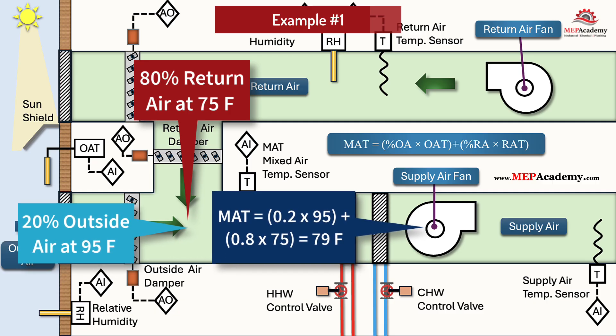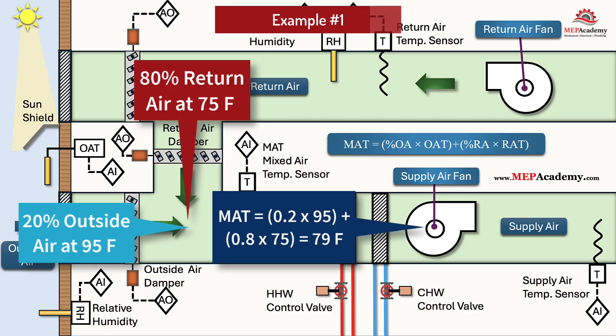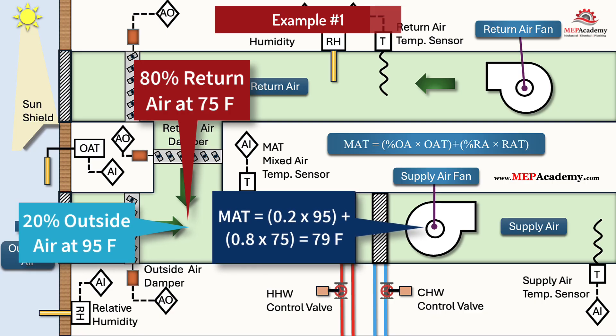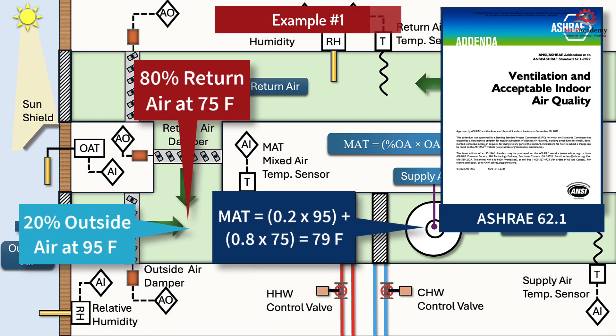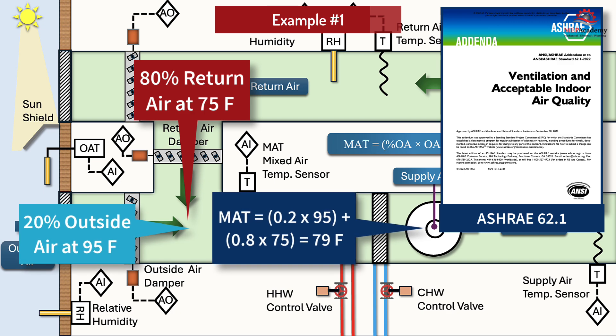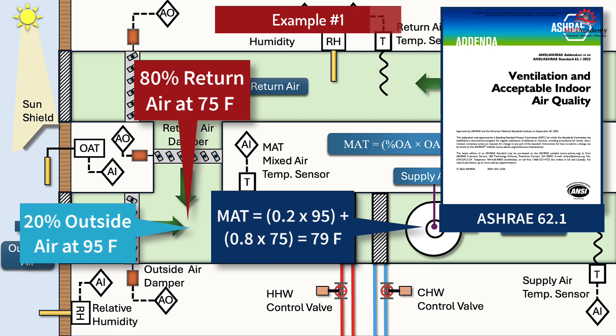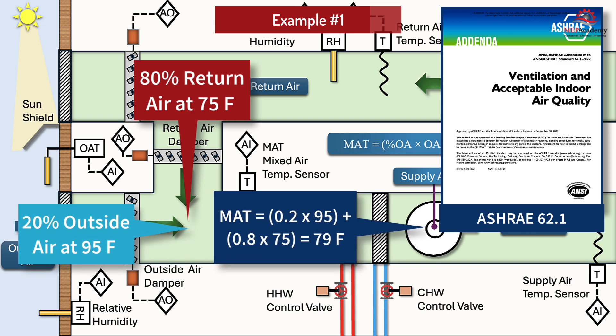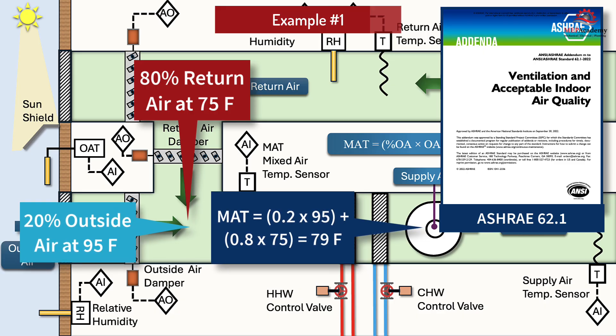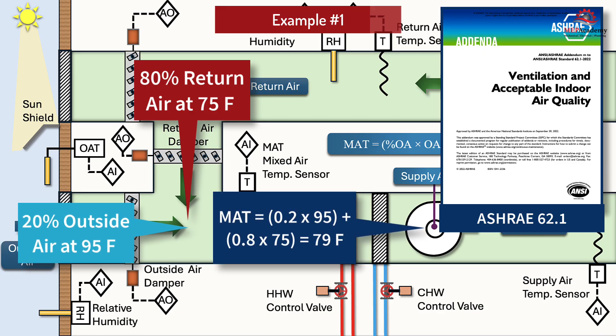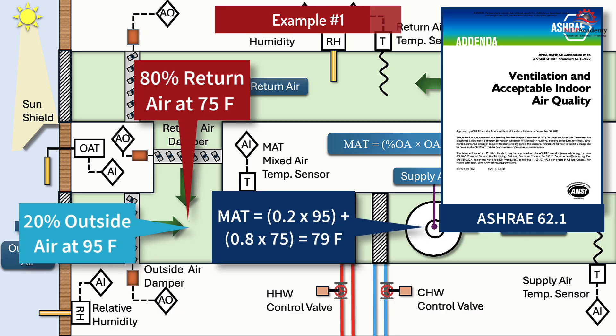In this case, since the outside air is way above the high limit for any economizer, the outside air would be set to the code minimum per ASHRAE 62.1. It makes no sense to waste energy cooling outdoor air at 95°F when the return air is at 75°F, not considering relative humidity.